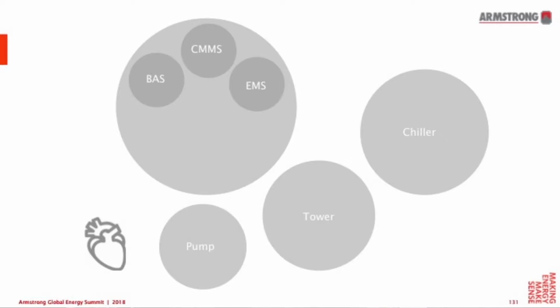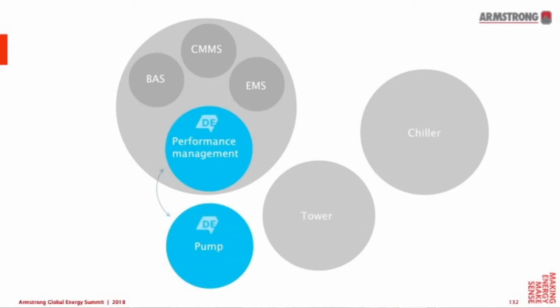So when we upgrade the pump, it immediately regulates the flow in the system. Most importantly, it actually starts giving us information about the equipment and the health of the system. And with the intelligent pump, you make all of that transparent to the building management system, whether it be the energy management system, the CMMS, or the BAS system. The pump, because it has built-in DE technology, starts saving energy from day one. That retrofit is guaranteed cash flow positive from day one.